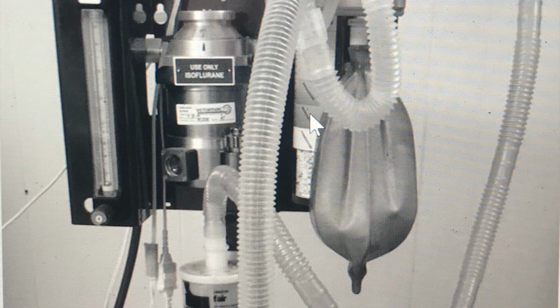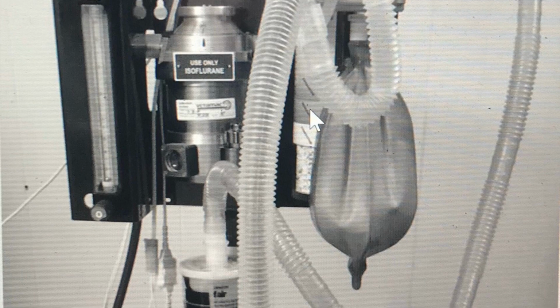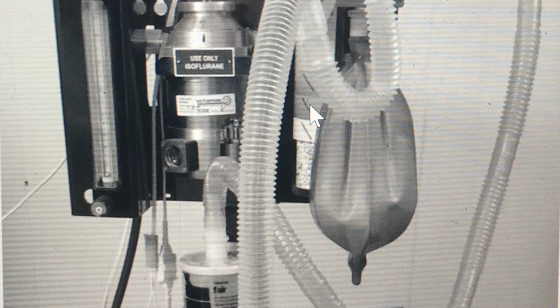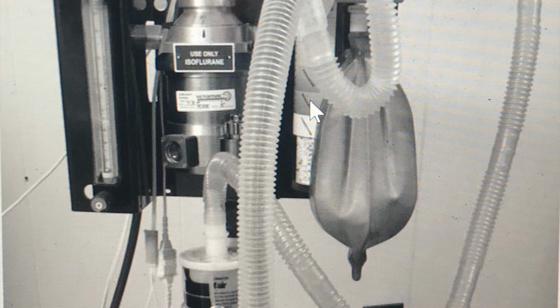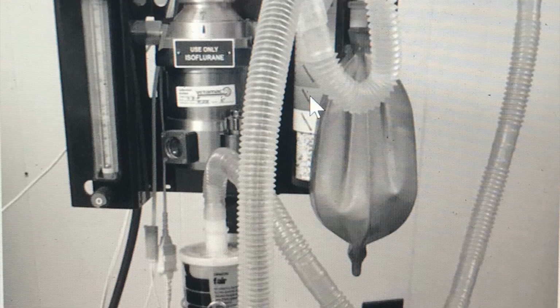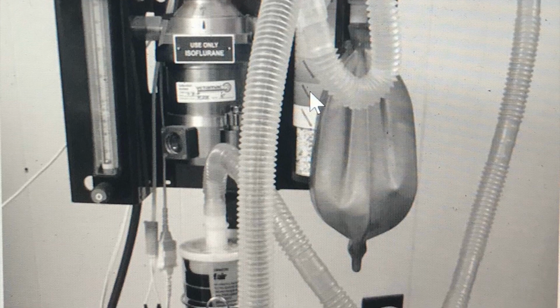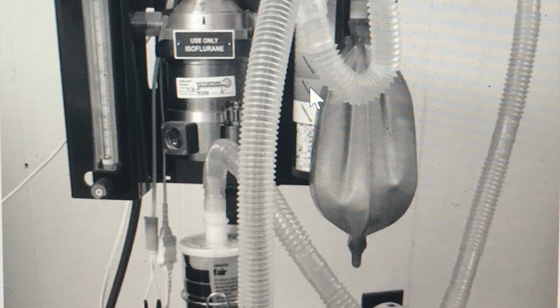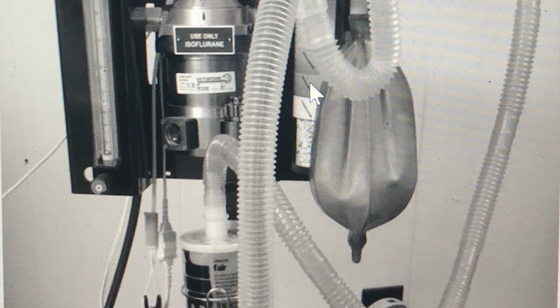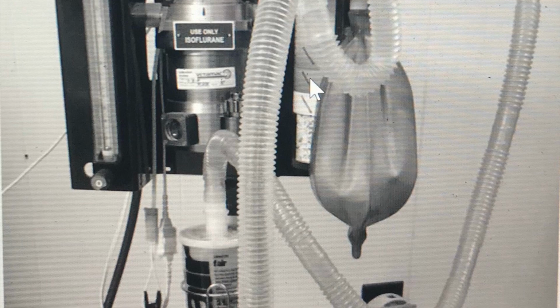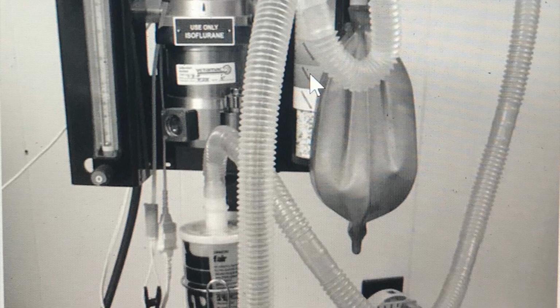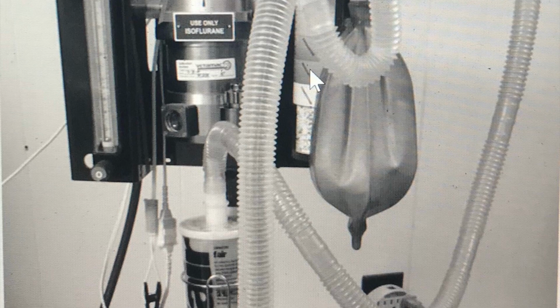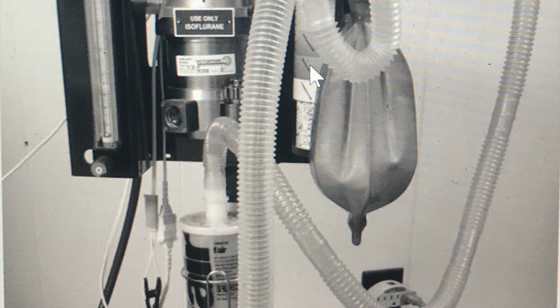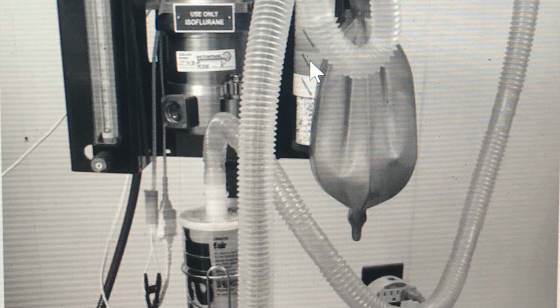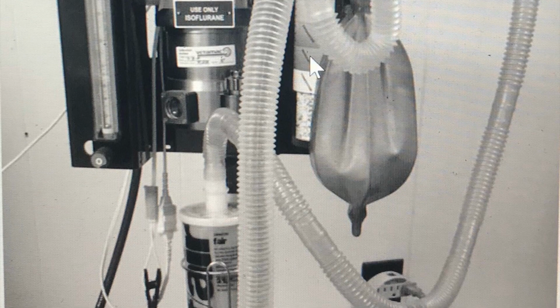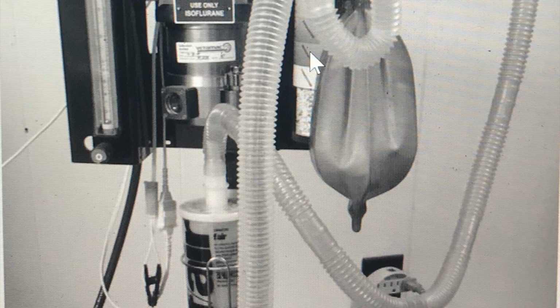At this point, you'll close your pop-off valve and occlude your patient's tubing that will connect to their endotracheal tube with either a finger or the palm of your hand. Then you will fill the system with oxygen using your O2 flush valve until the manometer is reading 30 centimeters of water. Your pressure shouldn't decline more than 10 centimeters of water in 30 seconds, and if this all checks out, then you can open your pop-off valve to release that pressure. Common sites for leaks would be your rebreathing bag, your one-way valves, hose connections, CO2 canister, if it's not tight enough, and if you find any leaks, you must fix them and recheck the machine. Do not use it if it's still leaking.